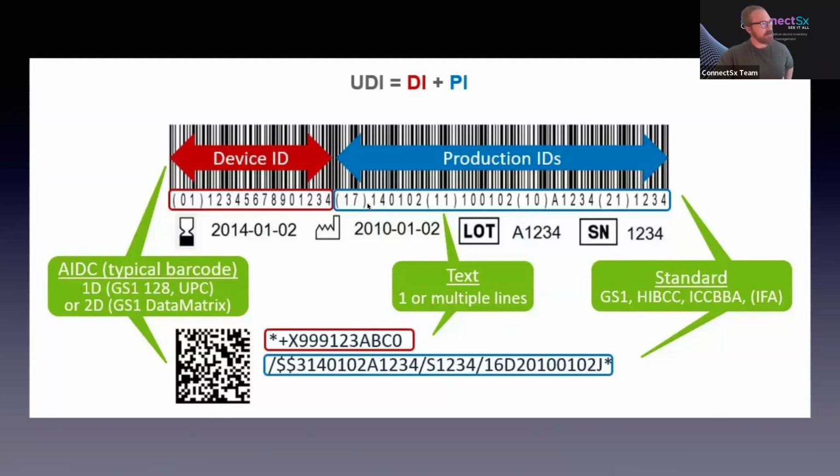And same here. I'm not exactly sure of all of these, but one of them would correspond to the lot, one probably to the expiration date. And, as a user of UDI, you don't need to know most of the time what these identifiers mean. You just need to be able to pass the UDI along, make sure it's valid, and then in some cases actually access the information that's contained within it. But if you're someone who builds UDIs or has to deal with issues that arise related to UDIs, then you might end up getting into that deeper level of detail.